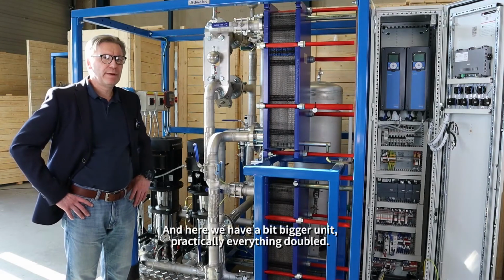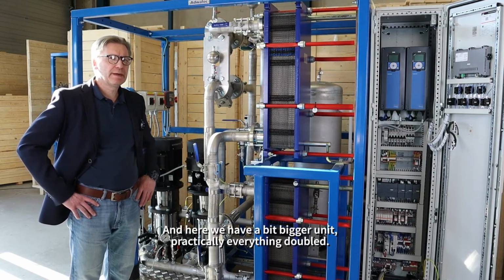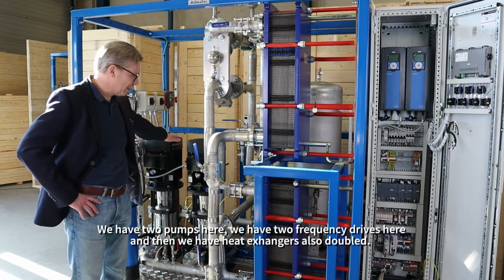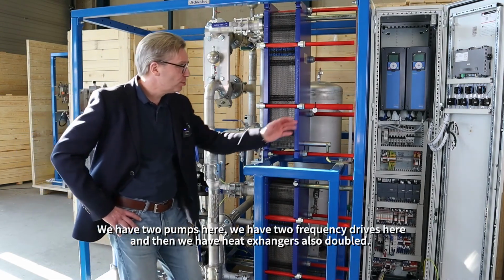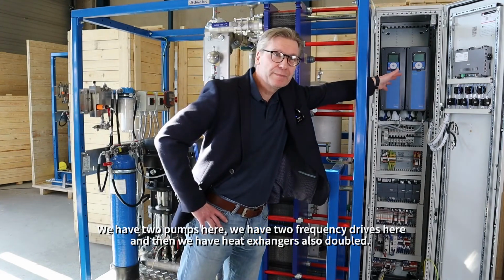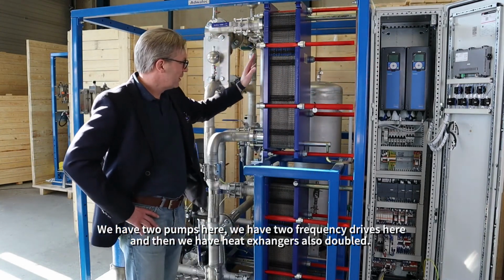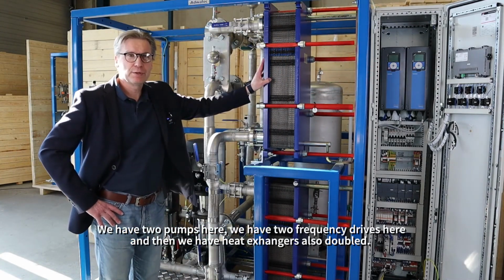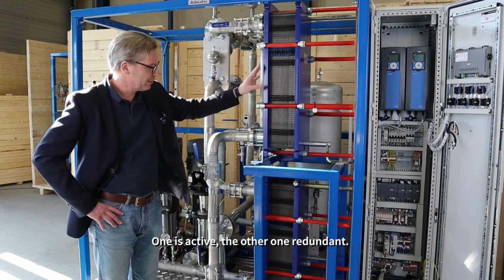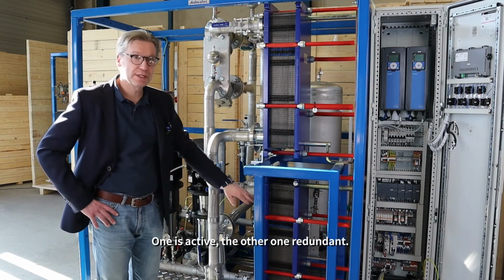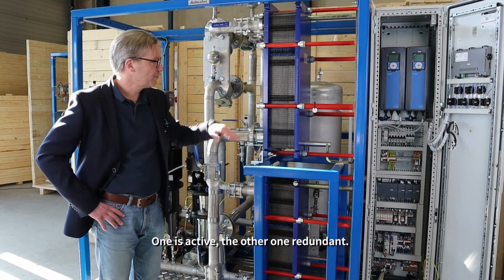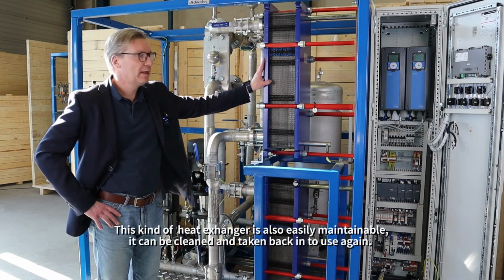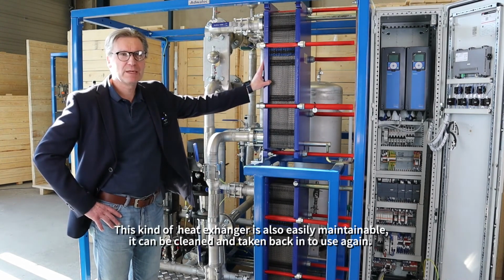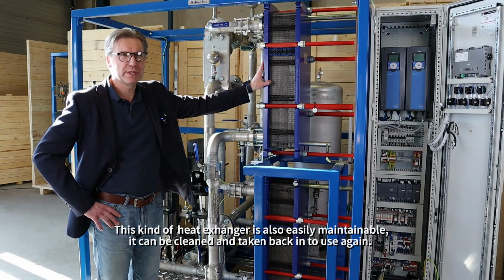And here we have a bit bigger unit, practically everything doubled. So we have 2 pumps here, we have 2 frequency drives here, and then we have heat exchangers also doubled. So one is active, the other one is redundant. This kind of heat exchanger is also easily maintainable, so it can be cleaned and taken back into use again.